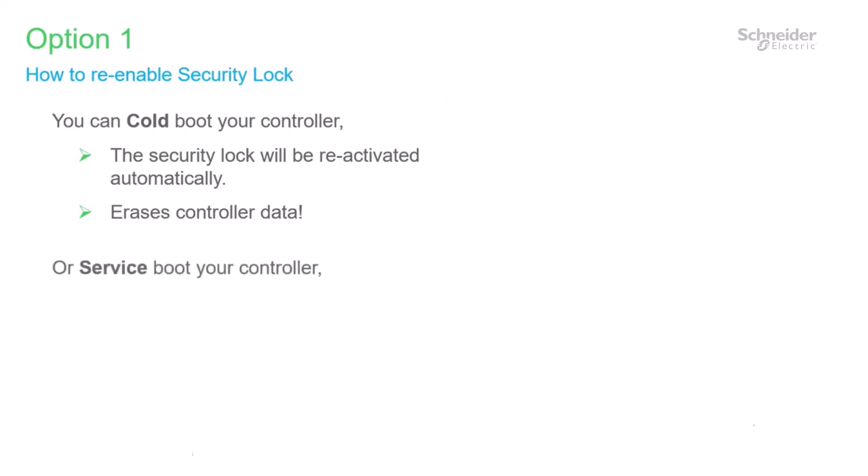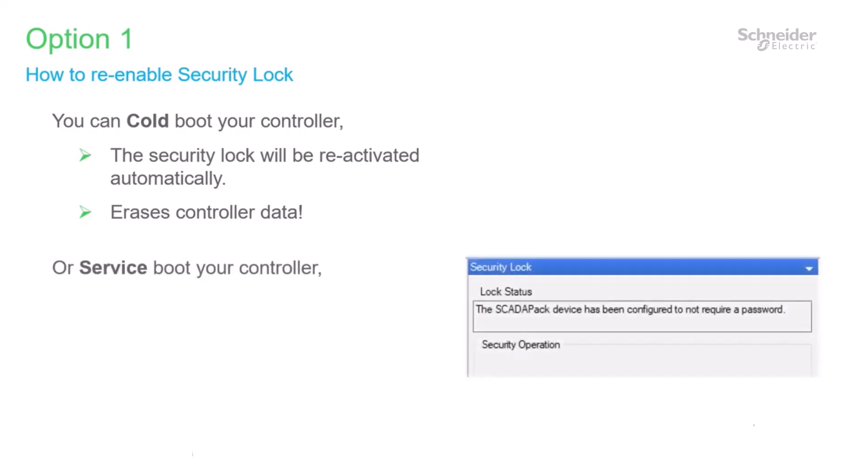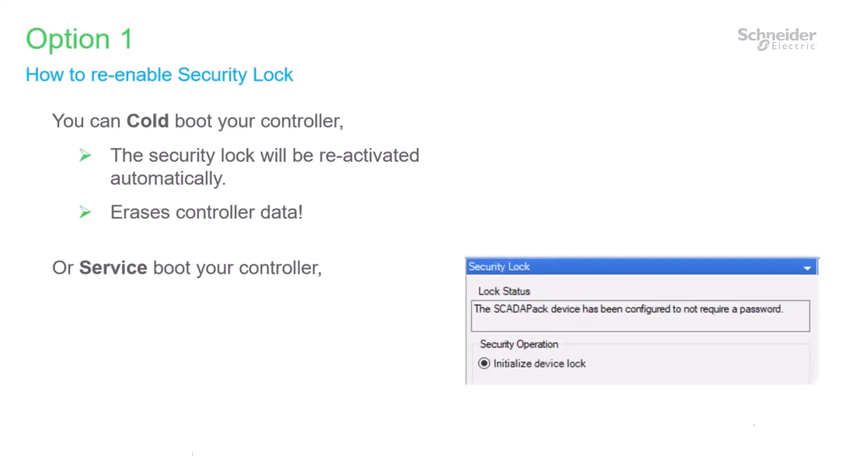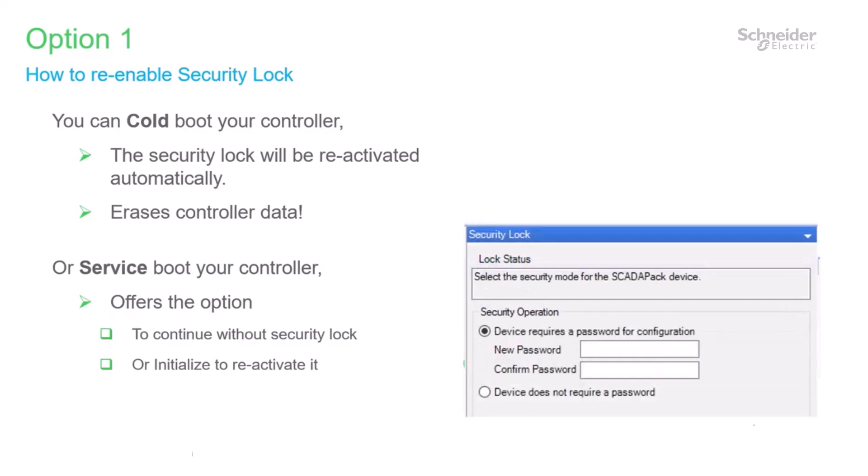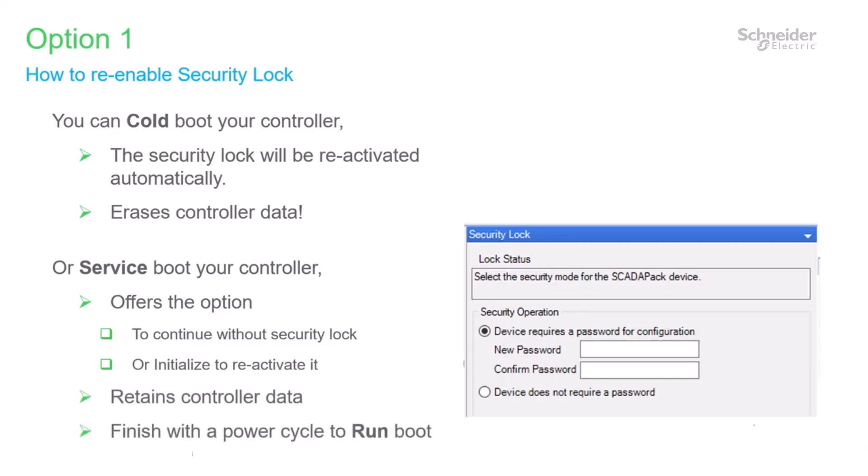So for the service boot, we again, before a service boot, we'll see that the controller doesn't require a password. When you do a service boot, that same menu will now show the option with the bullet initialize device lock. Selecting and applying this is the option that we have now. And what it does is reactivates the controller lock. Again, the same dialog now appears and you can apply the lock or disable it again. The advantage here is that the controller data has been retained. Remember though, that this is a service boot. So when you're finished, you're going to want to power cycle to execute a run boot so that the logic restarts.